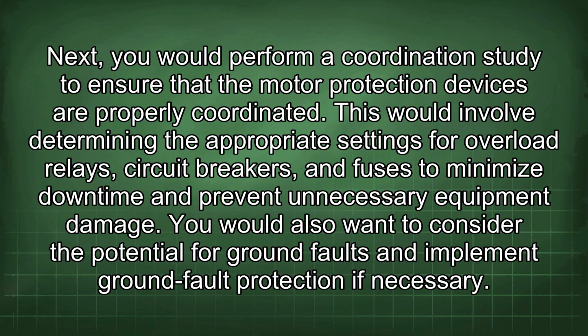Next, you would perform a coordination study to ensure that the motor protection devices are properly coordinated. This would involve determining the appropriate settings for overload relays, circuit breakers, and fuses to minimize downtime and prevent unnecessary equipment damage. You would also want to consider the potential for ground faults and implement ground fault protection if necessary.